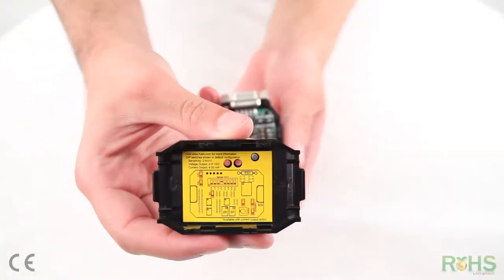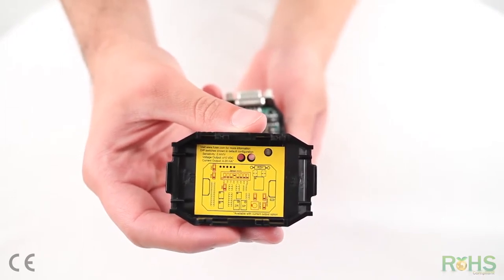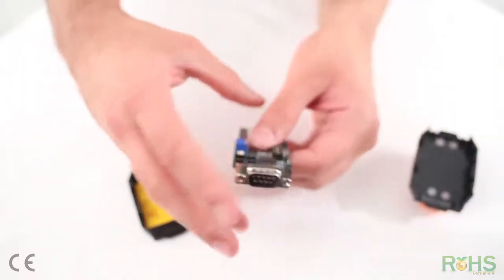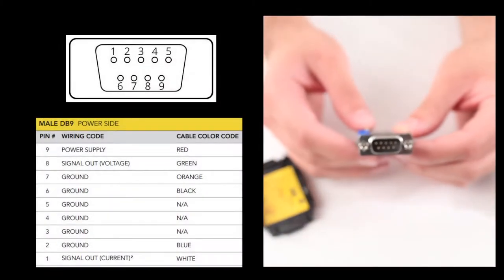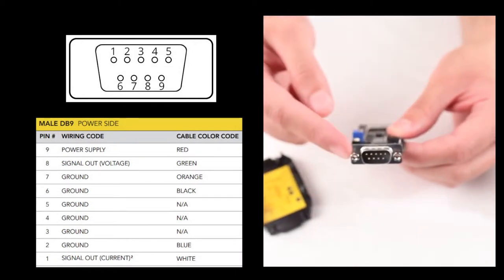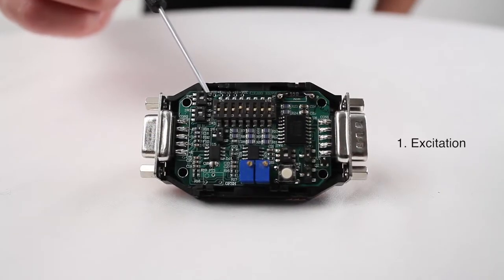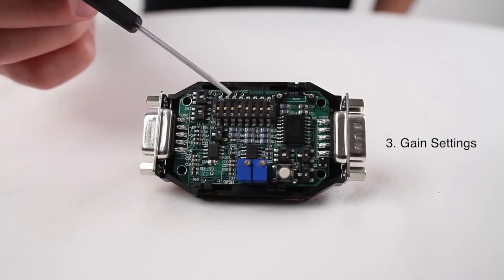On the back of your lid of your CSG110, you can find the default switch configurations for your CSG110. The CSG110 also contains one male and one female DB9. The male DB9 is used for your voltage input and also the voltage output is read from the same side. The female side of the DB9 is used for your sensor's input. Switch 1 is used for your excitation. Switch 2 is used for your polarity, and Switch 3 is used for your gain settings.